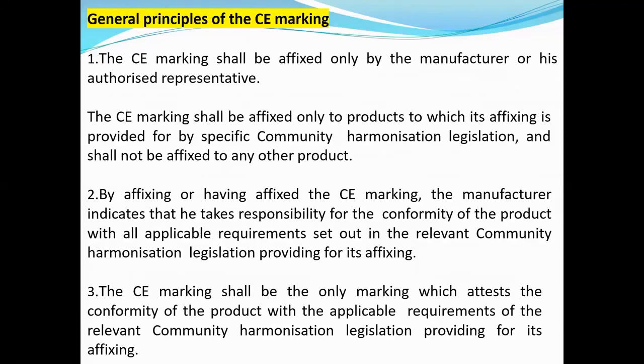Then CE marking shall be affixed only by the manufacturer or his authorized representative. The CE marking shall be affixed only to products to which its affixing is provided by specific community harmonization legislation and shall not be affixed to any other product. As I told you, if there are several components, it should be affixed only to the product to which its affixing is provided for by the specific community harmonization legislation.